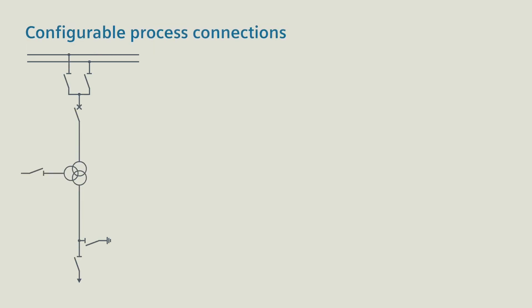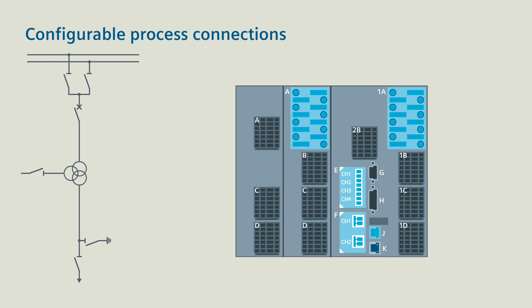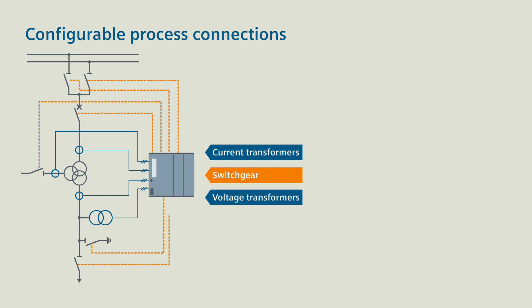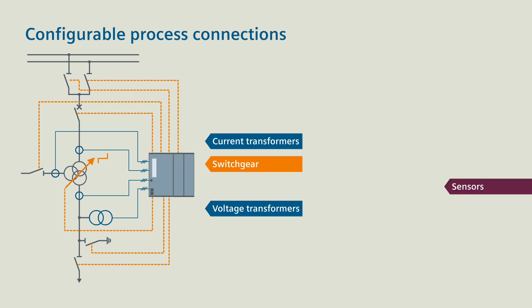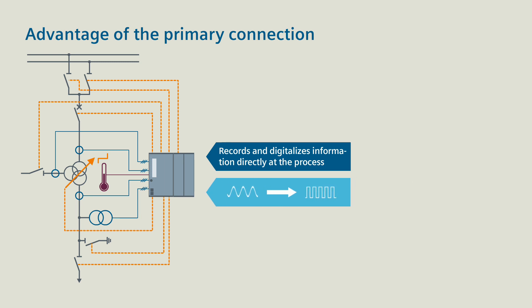An important prerequisite for an optimum primary connection is the requirement-specific configurable process connections of the SIPROTEC merging unit. These are, for example, connections for current transformers and voltage transformers in conventional form or in low-power design, connections for controlling and monitoring switchgear such as circuit breakers, isolators and tap changers, but also connections for various sensors for measuring temperature, pressure and other physical quantities. The advantage of this primary connection: the SIPROTEC merging unit records and digitalizes all information directly at the process.